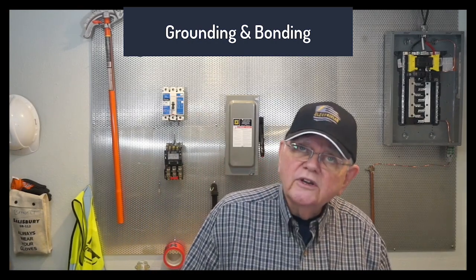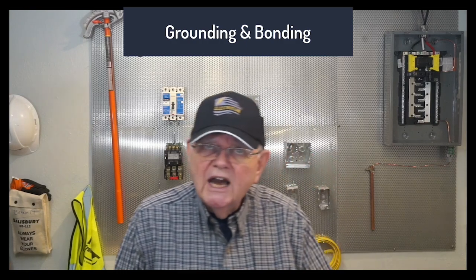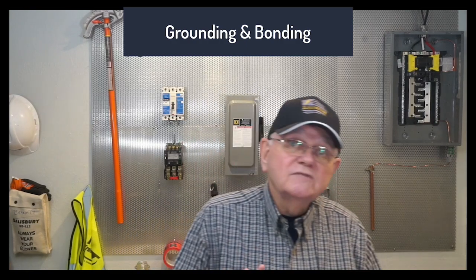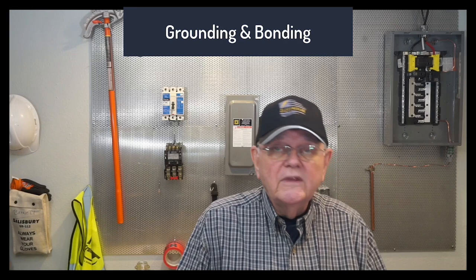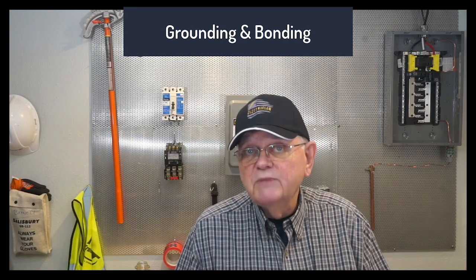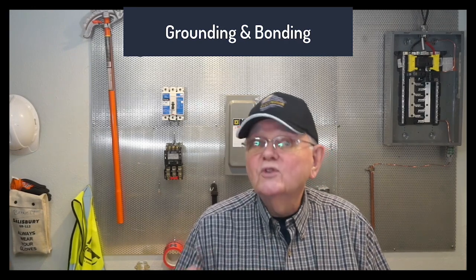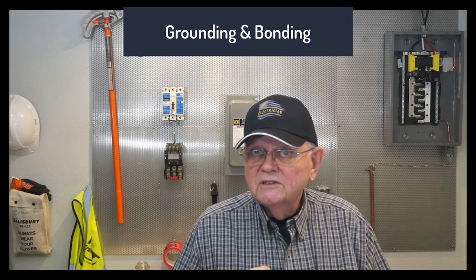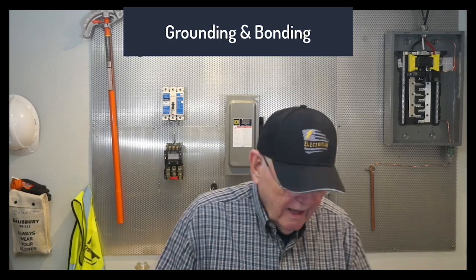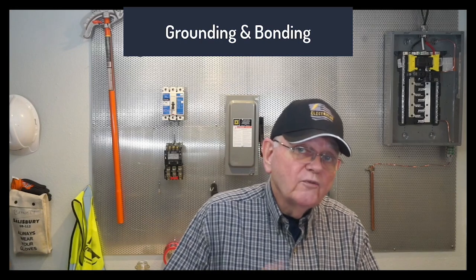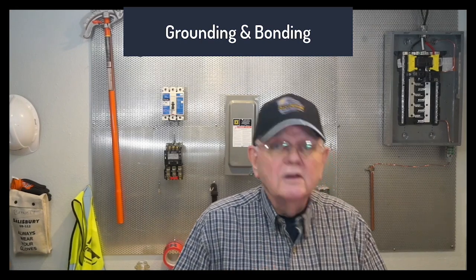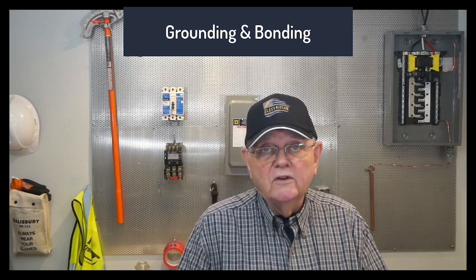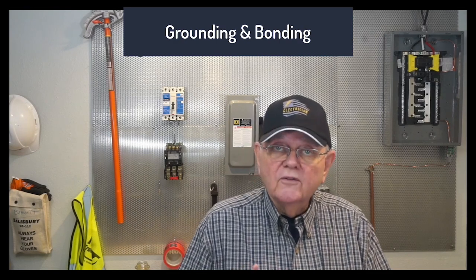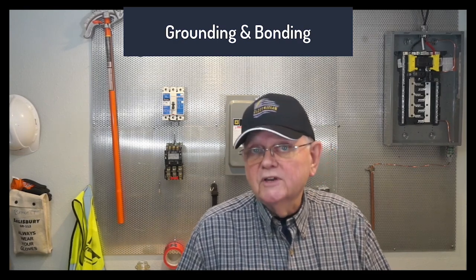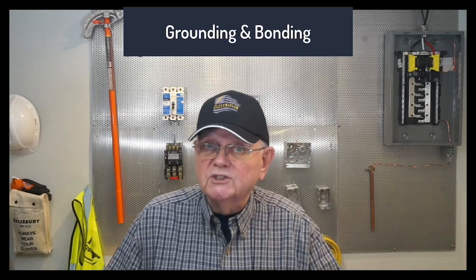Ground fault circuit interrupters, GFCIs. Remember, there are two classes of GFCIs we generally talk about. We talk about Class A and Class B. Class A is the one we use for personnel protection, trips at 4 to 6 milliamps. And remember, ground fault protection of equipment, which is defined in Article 100, is totally different from the ground fault circuit interrupters that we use for personnel protection, okay?